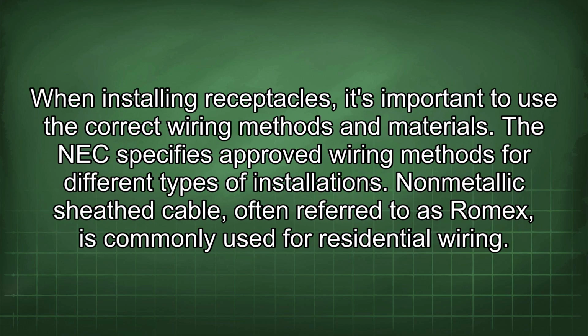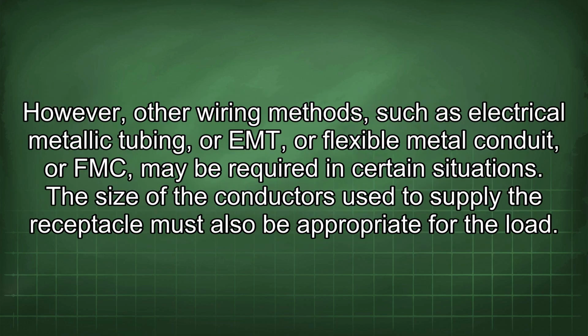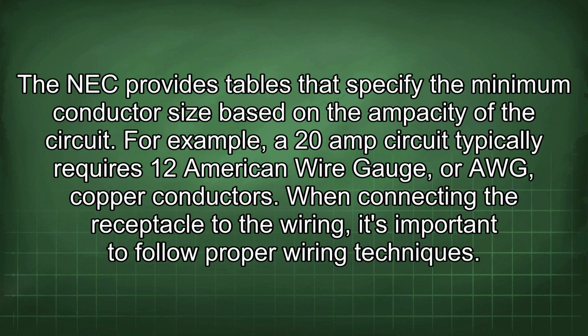When installing receptacles, it's important to use the correct wiring methods and materials. The NEC specifies approved wiring methods for different types of installations. Non-metallic sheathed cable, often referred to as Romex, is commonly used for residential wiring. However, other wiring methods, such as electrical metallic tubing, or EMT, or flexible metal conduit, or FMC, may be required in certain situations. The size of the conductors used to supply the receptacle must also be appropriate for the load. The NEC provides tables that specify the minimum conductor size based on the ampacity of the circuit. For example, a 20-amp circuit typically requires 12 American wire gauge, or AWG, copper conductors.